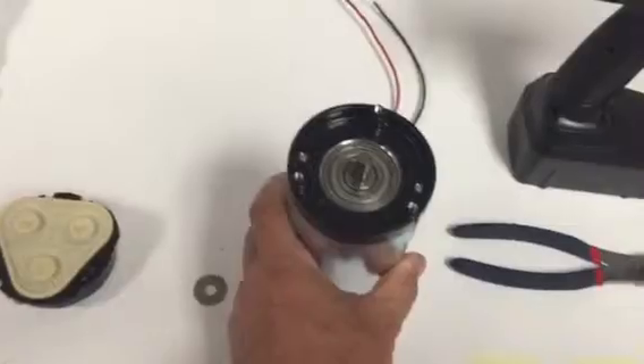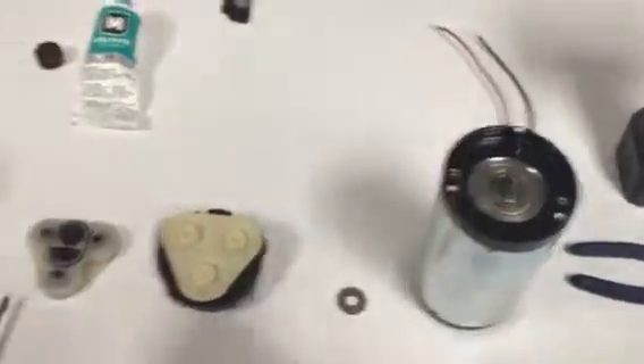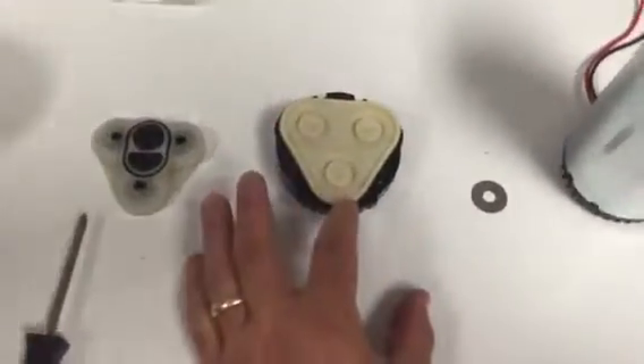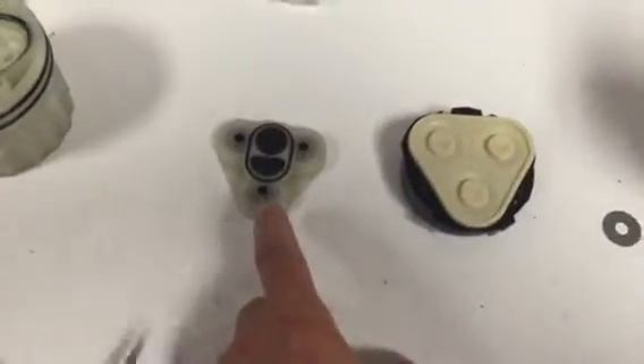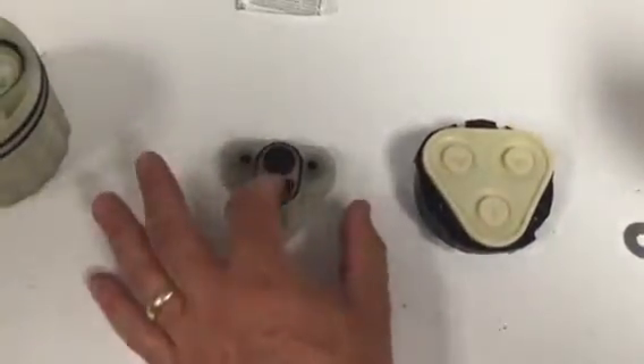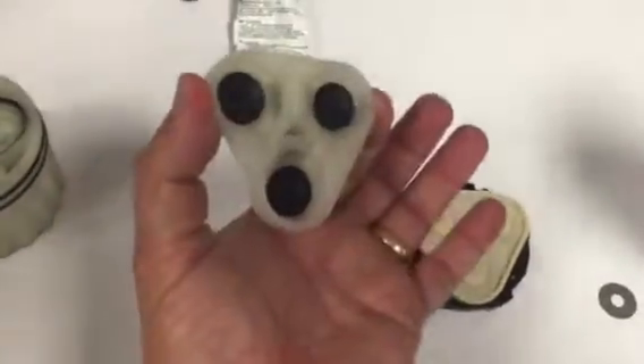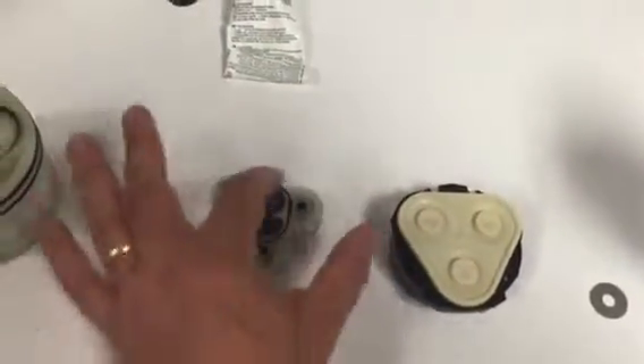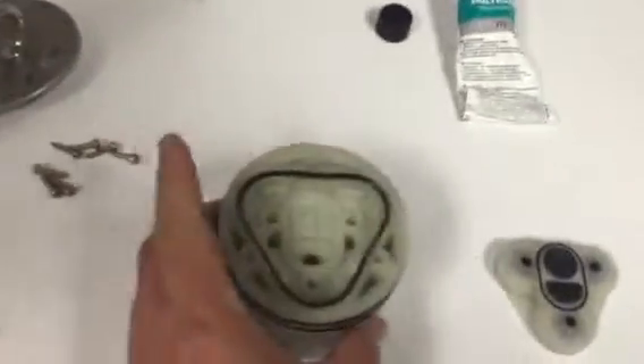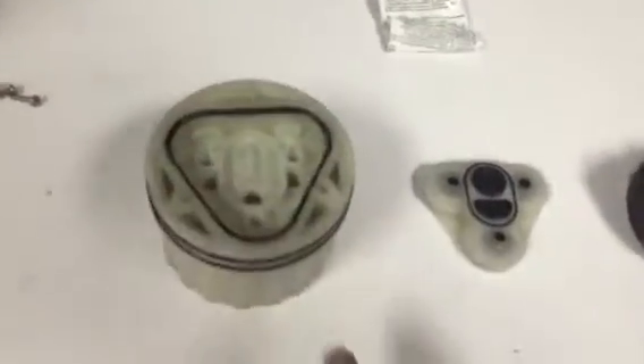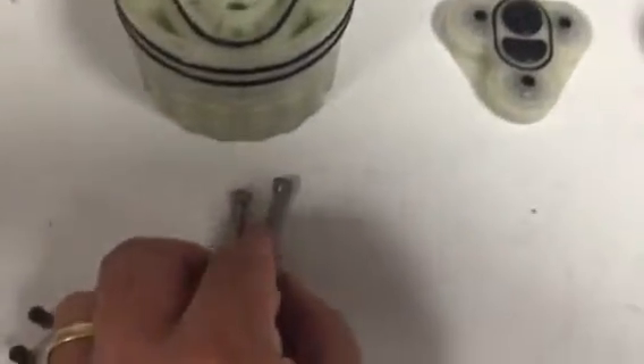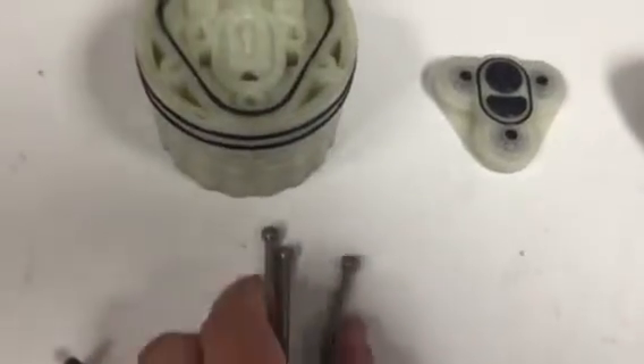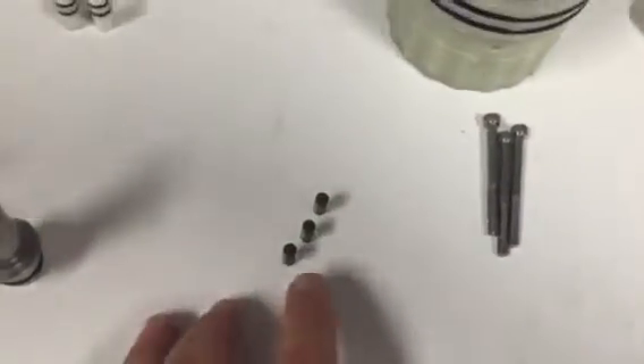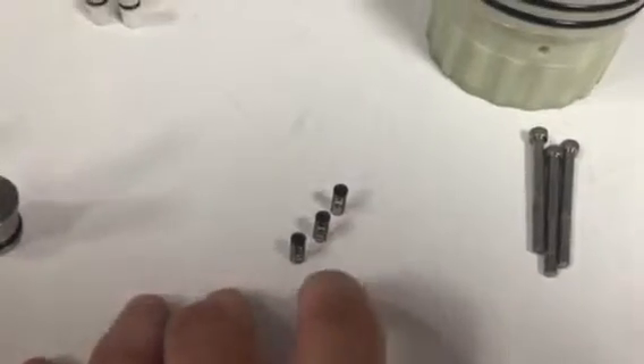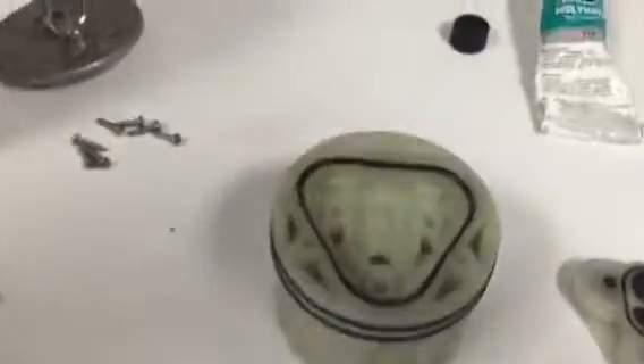We have the pump motor, the thrust washer that's going to go on the motor. We have a lower housing assembly, which includes the diaphragm, the valve housing assembly, which includes the full moon and half moon outlet valves, the 3 inlet valves, and the race O-ring. Then we have the pump head itself with the internal O-ring and the 2 outer O-ring seals. The 3 screws that attach the pump head to the motor assembly. We have the 3 springs and poppets that make up the bypass assembly, which will be placed into the pump.